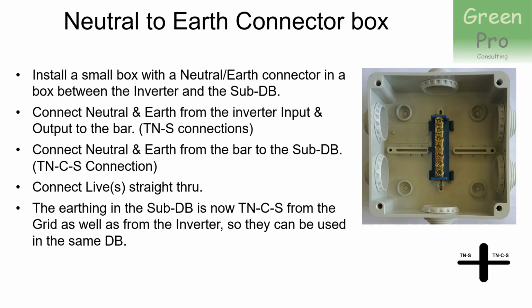Right. So this is how you do it. You install a small box, which has got no switching in, with a neutral earth connector in a little box between the inverter and the sub-DB. Then you connect the neutral and earth from the inverter input and the output of the inverter. You connect that to this bar. And those are your TNS connections.